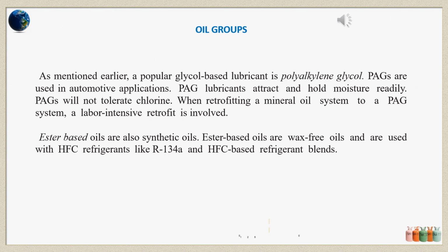As mentioned earlier, a popular glycol-based lubricant is polyalkylene glycol. PAGs are used in automotive applications. PAG lubricants attract and hold moisture readily. PAGs will not tolerate chlorine. When retrofitting a mineral oil system to a PAG system, a labor-intensive retrofit is involved.